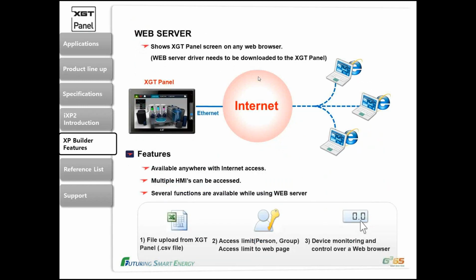We also have a web server. It's nice because you don't need to install any software on your computer. You only need to set up a driver on the XGT panel, the web server driver on your HMI. Once you connect it to the computer, you could pop in the IP address, use credentials to get into the HMI, and then access it. You can access multiple HMIs, as long as you have the IP address and credentials. There are multiple functions too, like device monitoring, control, and uploading different files from the XGT panel, like CSV files for trending and stuff like that.